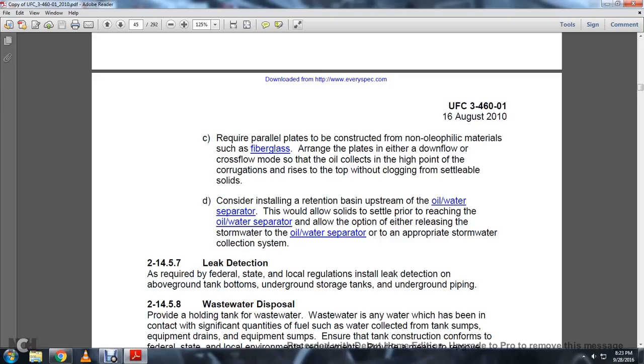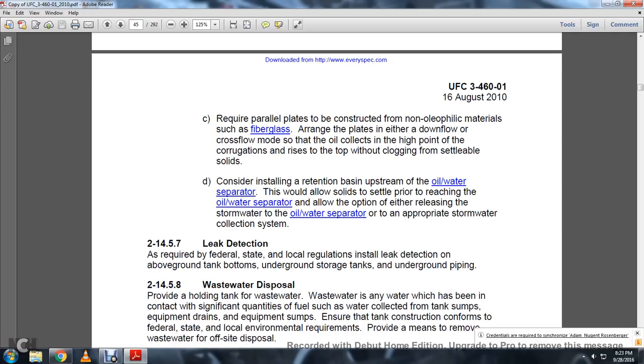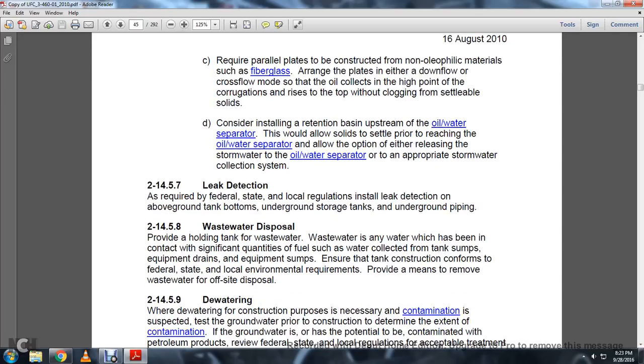Require parallel plates to be constructed with non-oleophilic materials such as fiberglass, arranged with the plates in either downflow or crossflow modes, such that oil collects in the high point of the corrugates and rises to the top, avoiding clogging from settleable solids. Consider installing a retention basin upstream of the oil water separator; this would also allow solids to settle prior to reaching the oil water separator. Release the storm water from the oil water separator to appropriate storm water collection systems.